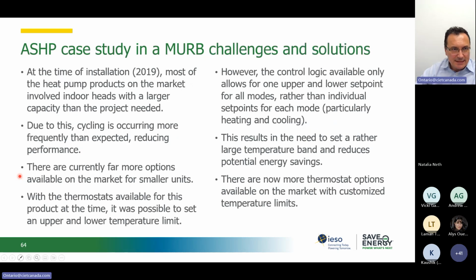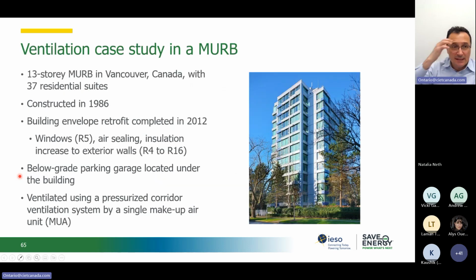I'll jump to the next example here, which is an example of a high-rise building. This is a 13-story multi-residential building in Vancouver. This had the building envelope project implemented, an upgrade on the window side, improving the air tightness, re-enveloping the building, increasing the R value from R4 to R16. We've added measures in the parking garage, and improved the control of the makeup air unit in the building as well.